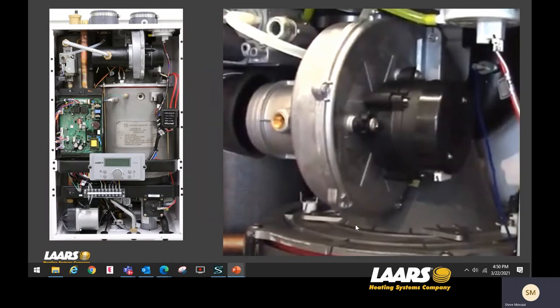With the top plate back in position, keep in mind we're bringing combustion air into a mixing station and fuel is also coming in. That gets drawn into the blower and down into the arm — if not properly sealed it will blow out inside the cabinet. If it's sealed on the front half but not on the back, you'll get some leakage and the gas leak detector will go off.